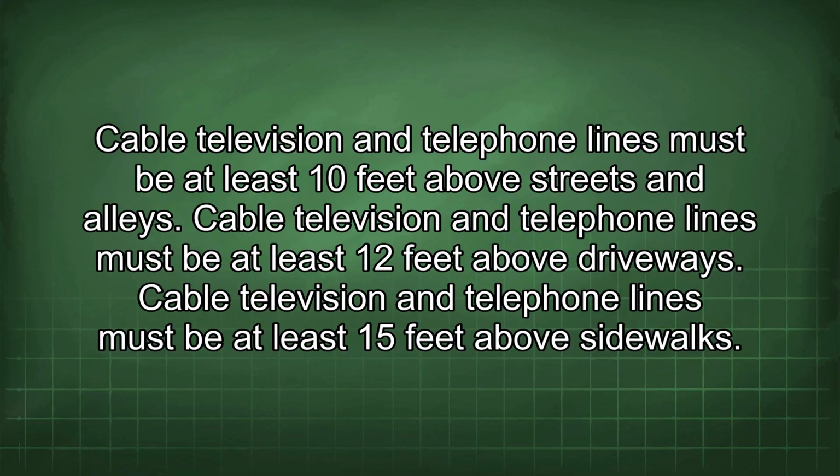Cable, television, and telephone lines must be at least 10 feet above streets and alleys. Cable, television, and telephone lines must be at least 12 feet above driveways. Cable, television, and telephone lines must be at least 15 feet above sidewalks.